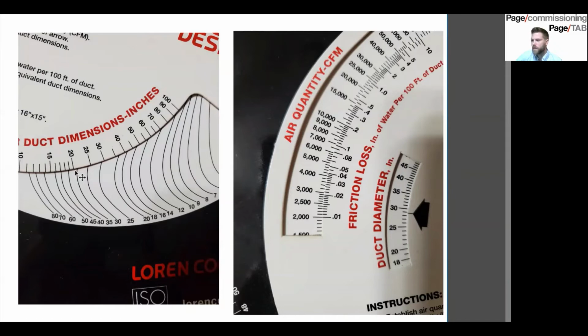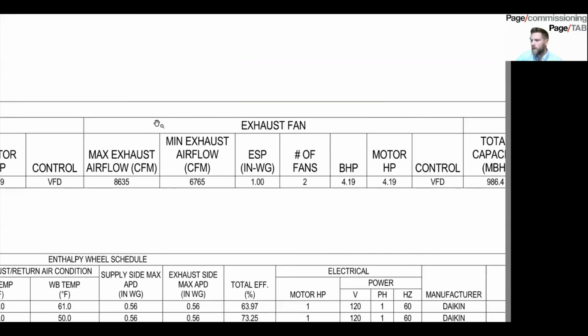So when you've lined that up, then you come over here and see what that 0.08 lines up with. And so you have 6,000, you're a little ahead of that. So maybe you're at 6,100. So that means 6,100 CFM is the ideal CFM or lower to flow through that ductwork. And we have 8,600 flowing through. So we have an issue, right? And so that's a quick catch. You're over 2,000, you're trying to flow over 2,000 CFM more through that ductwork than you should.